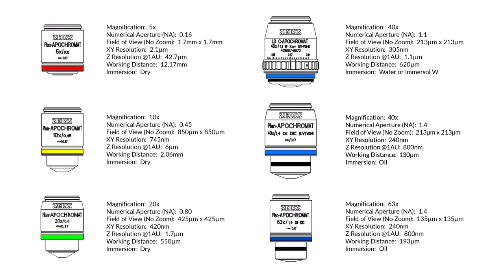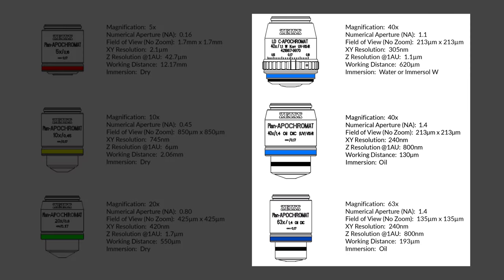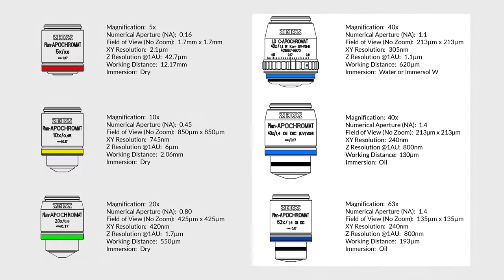Using an oil immersion objective with a specimen mounted in aqueous media, cell culture media for example, will significantly reduce the performance of the objective as you focus further into the specimen, and this problem will be readily apparent on a confocal microscope. If you require an immersion objective, choose one that closely matches the refractive index of your mounting medium for best results.